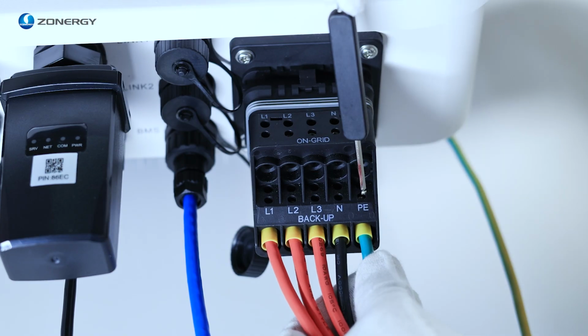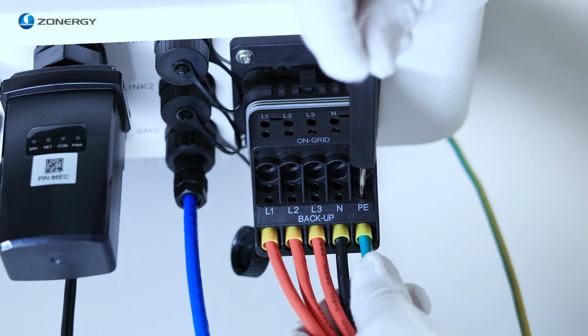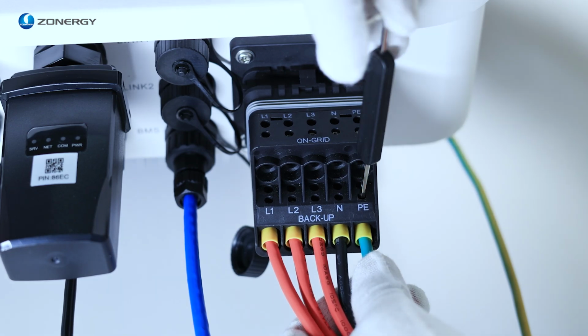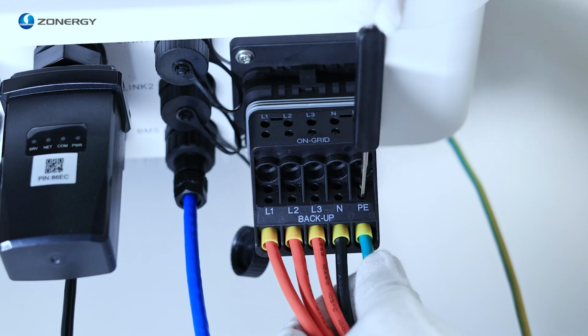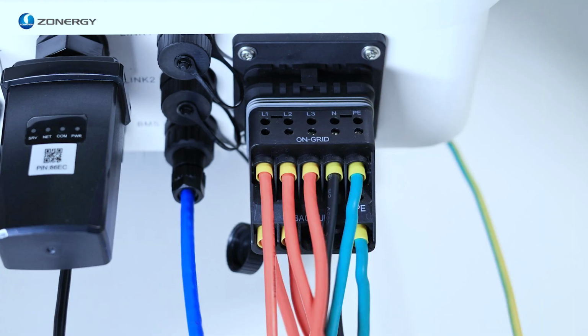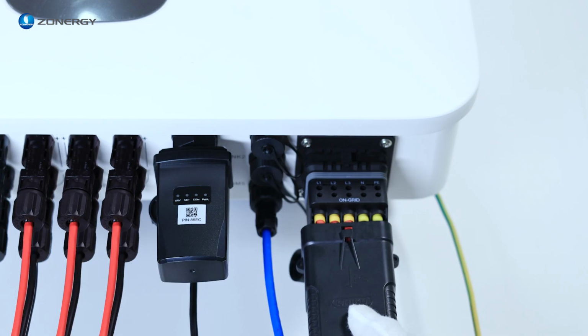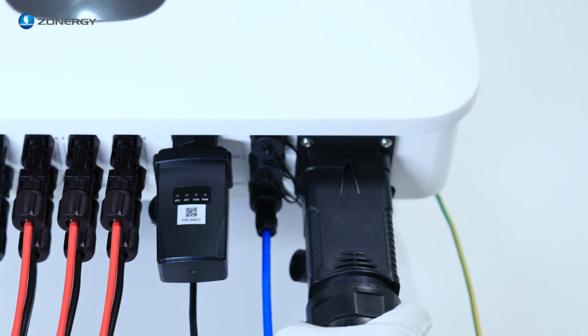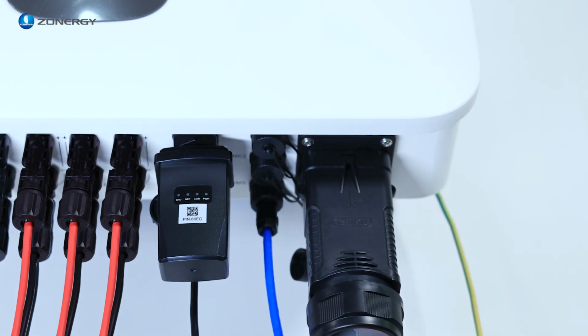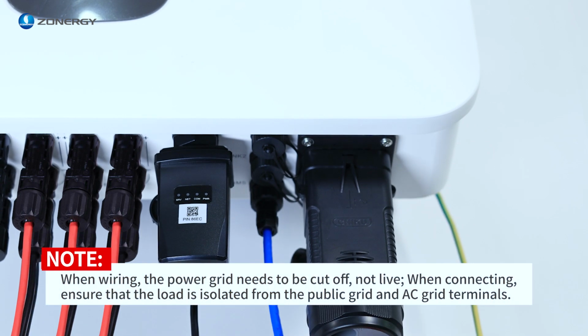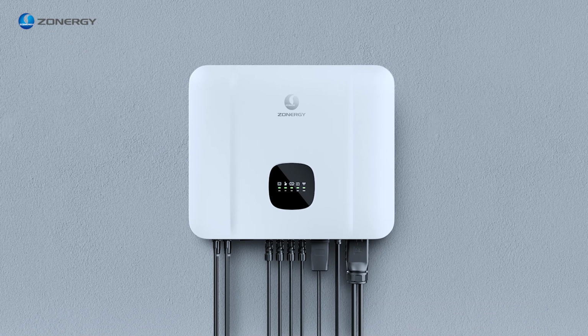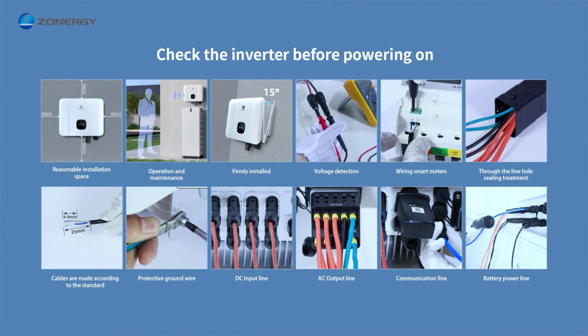9. Insert the cable into the backup and on-grid L1, L2, L3, and N terminals respectively according to the polarity indicated on the terminals and tighten the screws. 10. Push the protective cover onto the AC connection port and fasten it. Note, when wiring, the power grid needs to be cut off, not live. When connecting, ensure that the load is isolated from the public grid and AC grid terminals. The inverter has been connected. Step 7. Check the inverter before powering on.